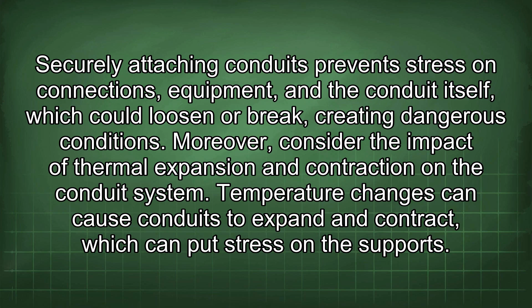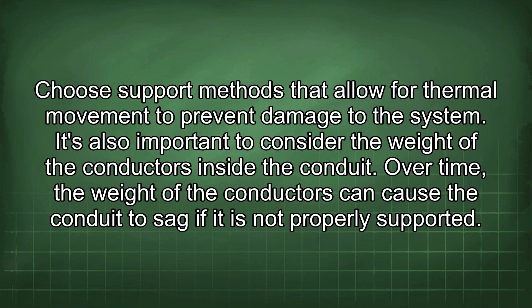It's also important to consider the weight of the conductors inside the conduit. Over time, the weight of the conductors can cause the conduit to sag if it is not properly supported. Ensure that the conduit is supported at appropriate intervals to prevent sagging and maintain the integrity of the system.